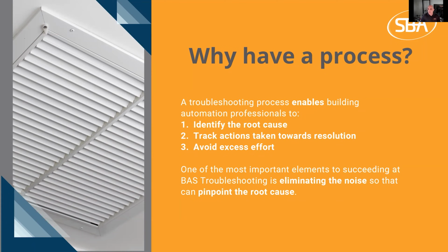One of the most important elements when you're troubleshooting is to eliminate all of this noise so that you can pinpoint the root cause. Because you're going to go to a job site and the customer is going to say, well, it never worked. It doesn't work. It's cold. It's hot. It's this. It's that. They're not going to tell you that they've been manually operating the valves in hand because that's what they feel most comfortable with, and they don't trust the BAS system. They're not going to tell you that they didn't want to pay for that retrofit from their contractor, so they tried to do a retrofit on their own.